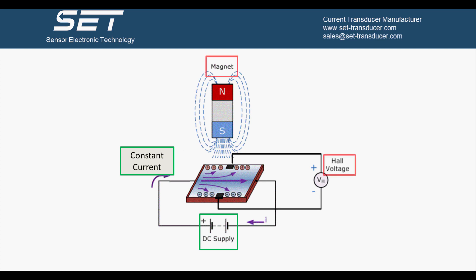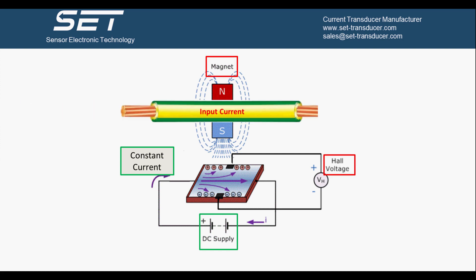In this case, the change of the Hall Voltage reflects the change of the magnetic field strength. The magnetic field is generated by the input current, which has a clear proportional relationship between the magnetic field and the input current. Therefore, by measuring the Hall Voltage value, the input current value can be derived. This is the basic principle of measuring current intensity using Hall Effect elements.